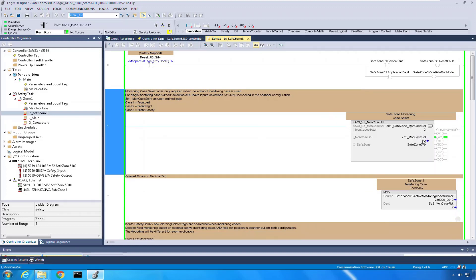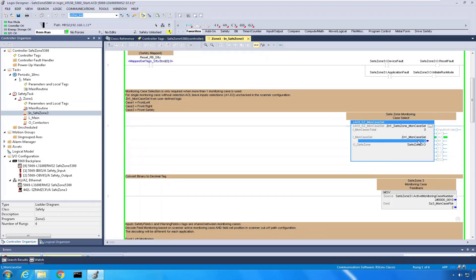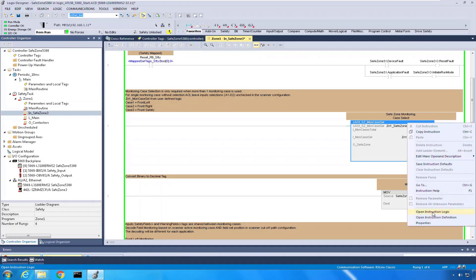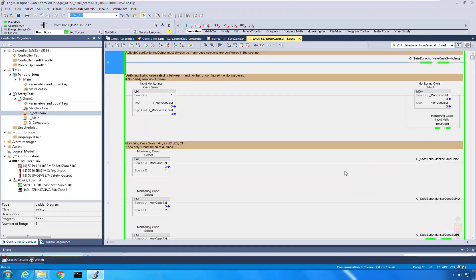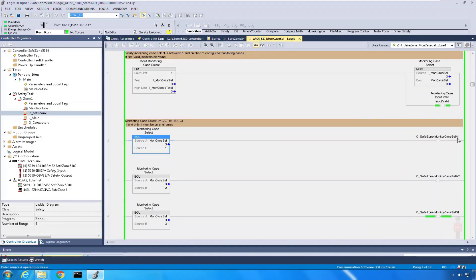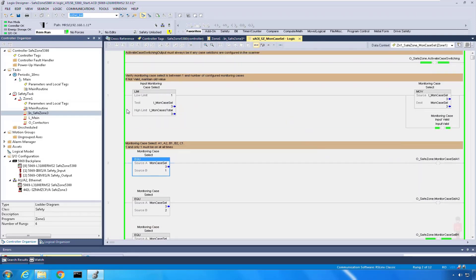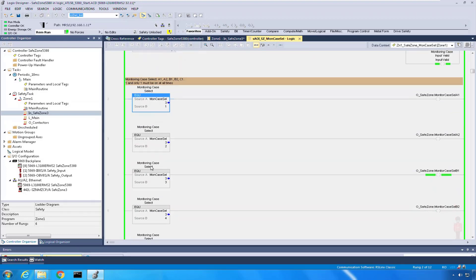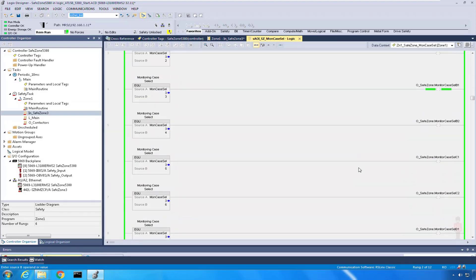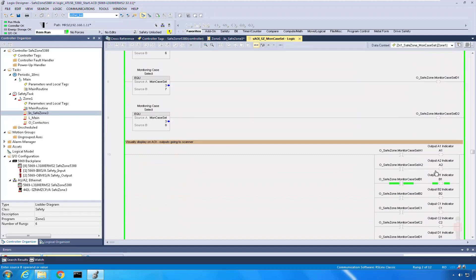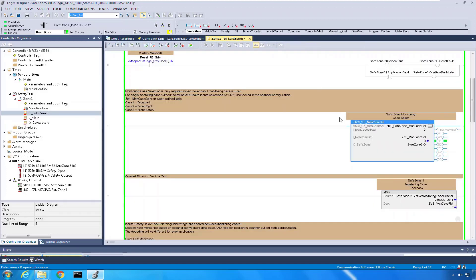Essentially it just says, if I do an integer selection of a monitoring case, if I go to 2, select A2. If I select 1, then I'm going to go A1 A2. It's just a couple move statements. We can actually look at that and see the instruction logic, but it just says if that's selected, output the different cases. It also limits the cases, so if I have 3, don't select something else because the scanner is not configured to do so. Just if I'm equal to 3, output B1 like I am there, and provide some indication of what you're doing. That's all the AOI is doing—taking a digital input and writing it into that Safe Zone 3 tag for A1, A2, B1, B2, etc., the cases that I have.